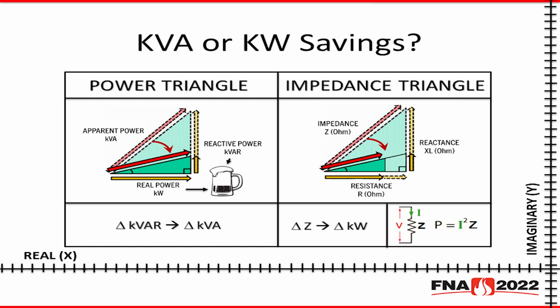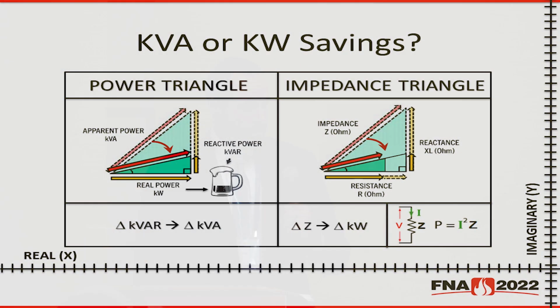On the x-axis, you have kW. That's the real power, the power that's doing work in a process. And then on the vertical y-axis, you have kVAR, which is the reactive power that's not doing work. The action shown here in the triangle is what we discussed in case 1. When you have a reduction in kVAR with the same kW, you have a reduction in the overall kVA. So what about kW savings?